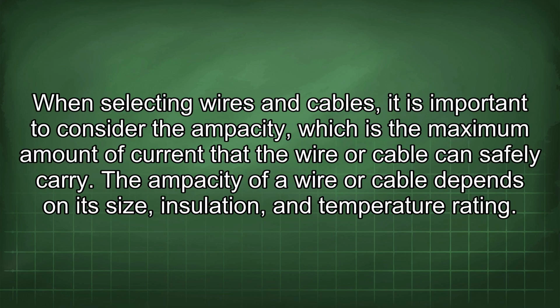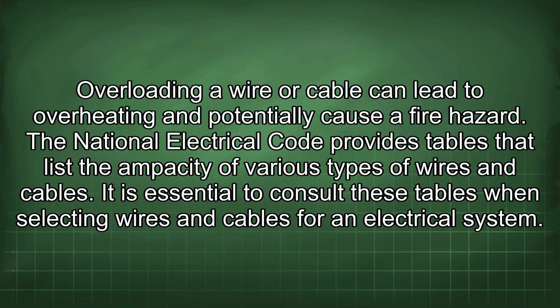When selecting wires and cables, it is important to consider the ampacity, which is the maximum amount of current that the wire or cable can safely carry. The ampacity of a wire or cable depends on its size, insulation, and temperature rating. Overloading a wire or cable can lead to overheating and potentially cause a fire hazard. The National Electrical Code provides tables that list the ampacity of various types of wires and cables. It is essential to consult these tables when selecting wires and cables for an electrical system.